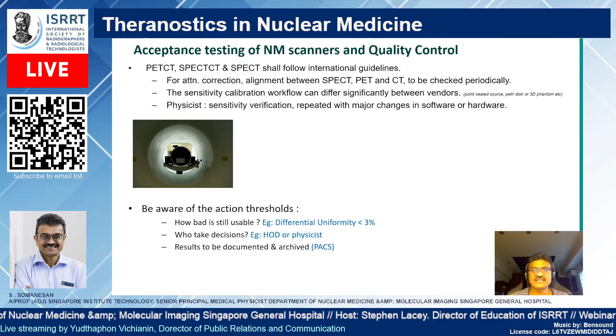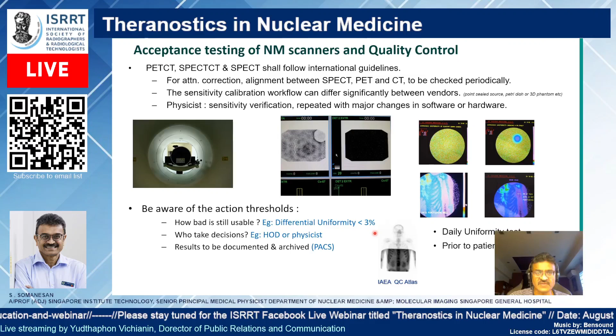And of course, if you can look at this, it is a poor uniformity image of the yesteryears when we were using circular detectors. This is from the IAEA Quality Control Atlas, where you can see there's an artifact as a result. Okay, so of course, as technologists and radiographers, we need to be aware of the action thresholds. For example, how bad is bad? How bad is it still usable? For example, on a daily differential uniformity, is it less than 3%? If it is, then it's acceptable for use in SPECT imaging as well as planar imaging. If it is greater than 3%, then something warrants being checked, and perhaps you need to call in the physicist or the engineer to take a look at the detector, right?